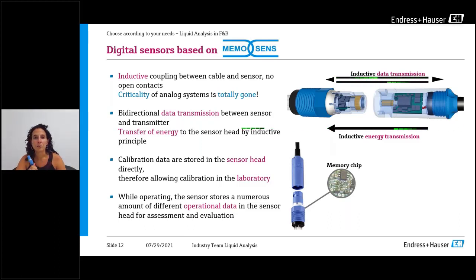This sensor can be calibrated anywhere, not necessarily in the process. And then I can bring the calibrated sensor to the process, take the other one, put this one to measure, and the other one, I calibrate that sensor whenever I have time. And that allows us to have a high availability of the measuring point, and also to make the calibration in a comfortable environment, let's say.